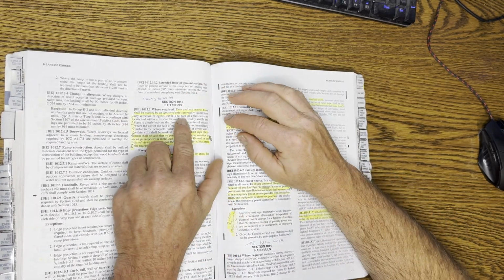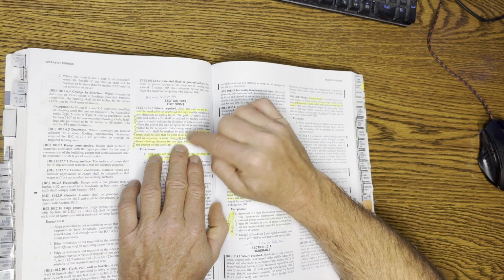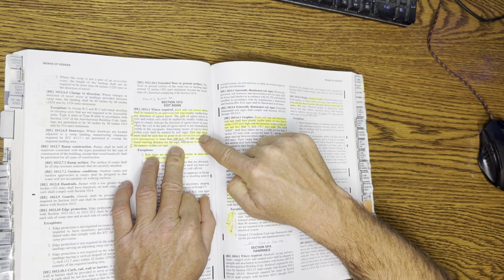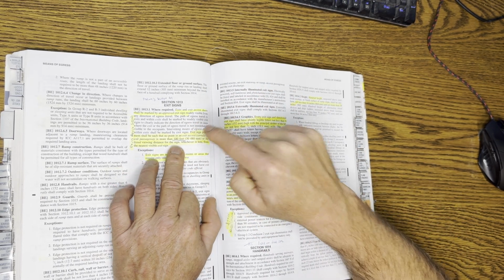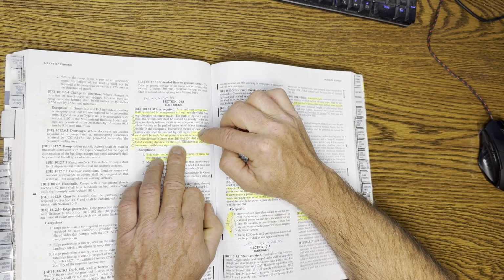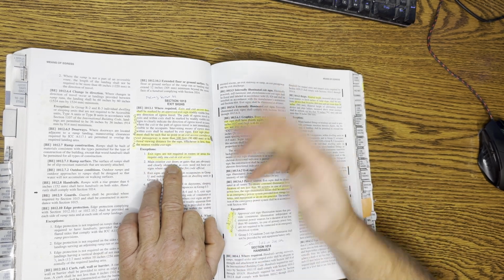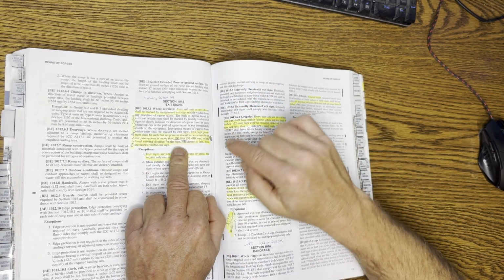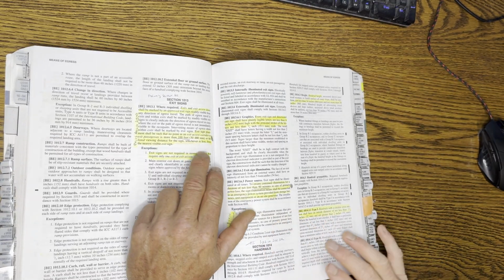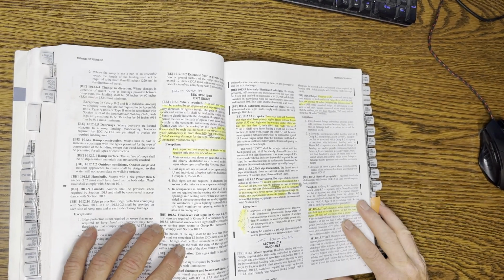Okay, exit signs, exit and exit access doors. Okay, so basically 100 feet. So in a corridor, I want to be clear, this is exit access corridors, or passageways. This isn't aisles. I want to be very clear about that. So anywhere within an exit access corridor, you need to be able to see an exit sign within 100 feet unless the exit's obvious. So just 100 feet, this is a test question. Does not apply to aisles necessarily or factory industrial occupancy. So don't get confused by that.